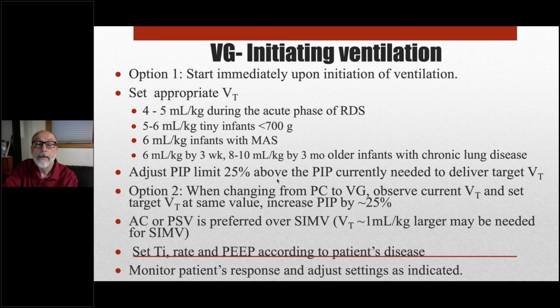So again, since volume is the primary control variable, the pressure needs to be able to float up and down. We know that on average, the pressure generated by the ventilator will be the same or lower than with pressure controlled ventilation. Okay, but it has to be able to go up and down because the baby breathes intermittently, and sometimes the ventilator is the only thing generating tidal volume, and will need to use a bit higher pressure.